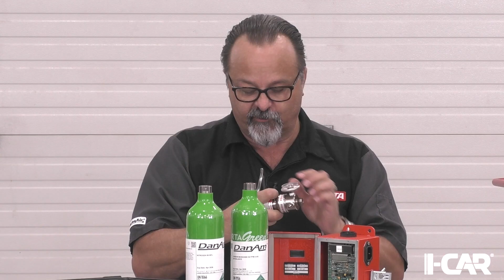This kit has a 50 parts per million carbon monoxide bottle, and on the monitor there's a screw called span. We connected a simple pressure valve with a port to an air hose, which screws onto the top of the carbon monoxide bottle. That hooks into the port on the side at the bottom of the CO monitor, and you open the valve, which is either on or off. There's no potentiometer or flow gauge to adjust. We watched the numbers go up right to 50 pretty quickly.